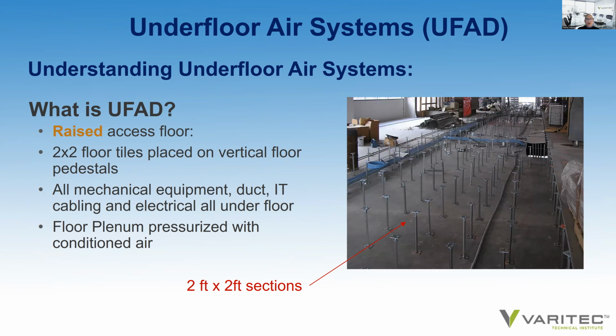How is this done? A UFAD system uses a raised access floor approach, whereby 2x2 floor panels are mounted on pedestals within a space. All mechanical, duct, IT cabling, and electrical are under the floor. There's no reason for maintenance crews to get up on ladders to service any part of an HVAC system or any other serviceable item within that space or within the building. The plenum then is pressurized with air in order to cause air to flow through underfloor air diffusers that are located in the floor panels throughout the building.